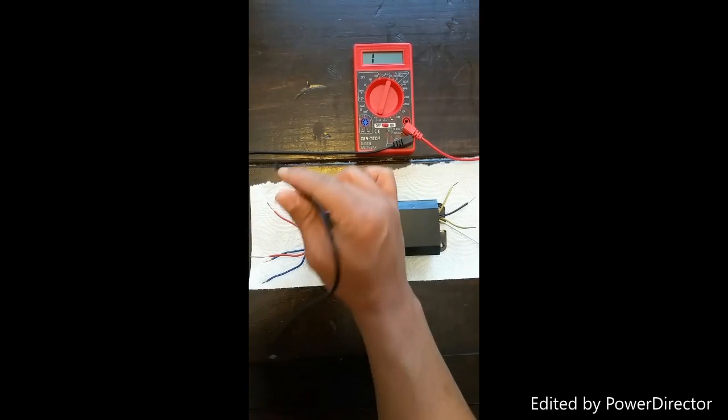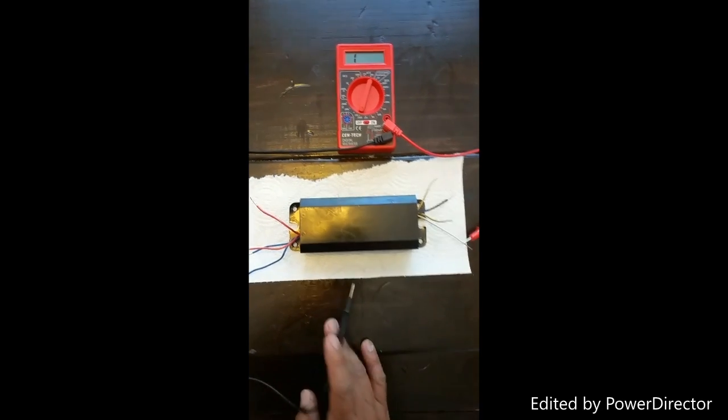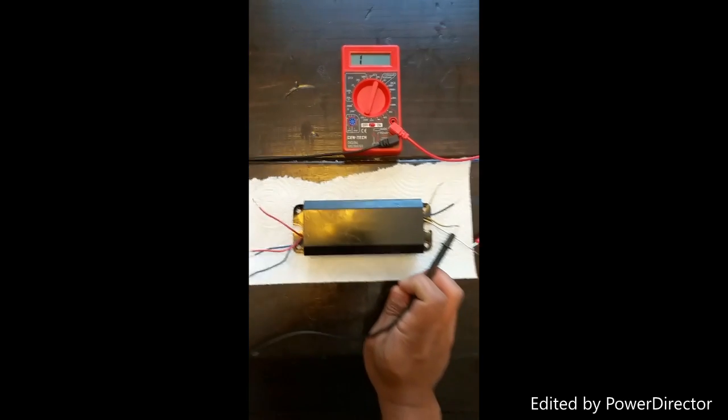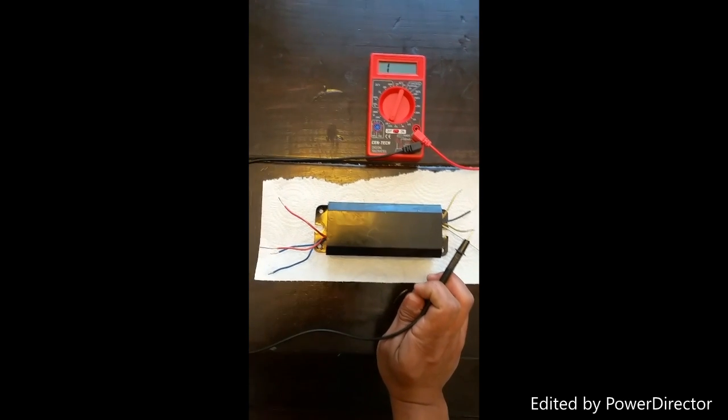Let me check the other red one here - and that one is too. So this ballast is bad and that's how you know if you need a new one.